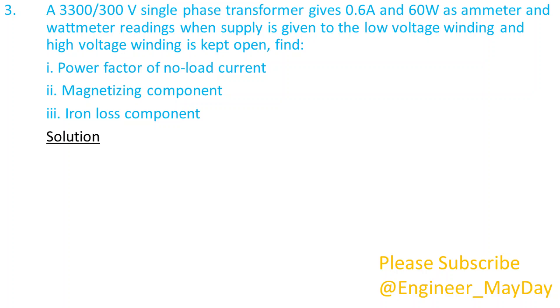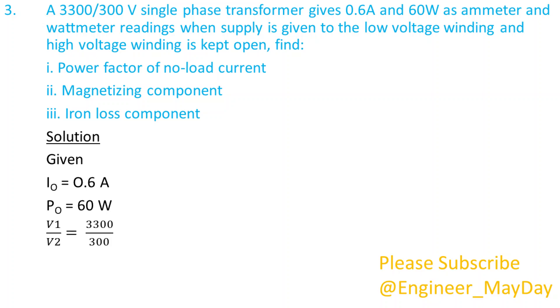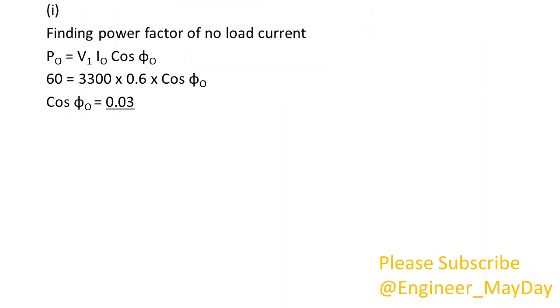Solution. Given: I0 equals 0.6 ampere. P0 equals 60 watts. V1 over V2 equals 3,300 over 300. 1. Finding power factor of no-load current: cos phi-0 equals 0.03.